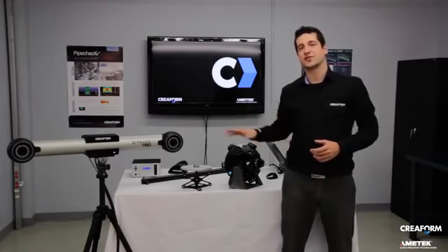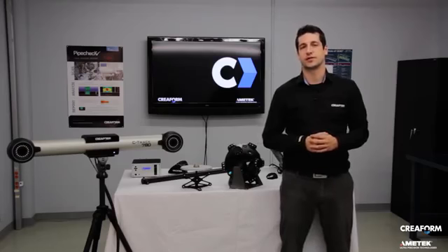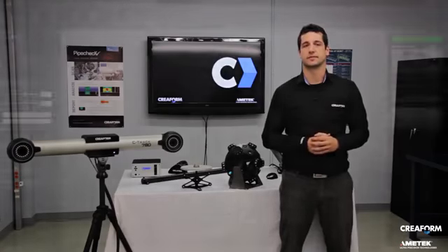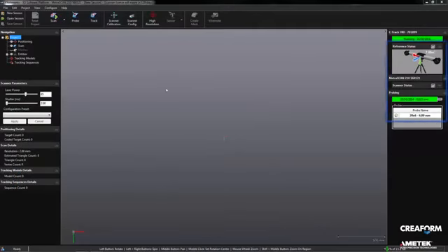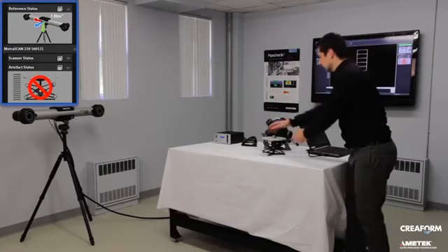The calibration of the MetraSCAN is as easy as the C-track's. All you have to do is launch the calibration wizard by clicking on the calibration button. Like the C-track calibration, the scanner calibration is done through a wizard, which once again reduces the human error.